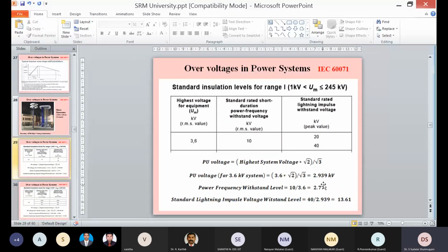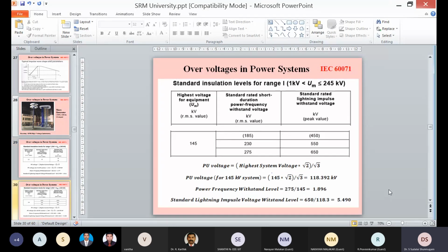Here the key point to be noted is how much increase is happening. For a 3.6 kV system, power frequency withstand level is 2.77 times higher. Lightning impulse is 13.61 times higher. This value please note down. This will be gradually reducing when you are moving to higher and higher voltage. I repeat, the level you are considering will gradually reduce as you move to higher and higher voltage. For example, the next calculation I have shown is for a 145 kV system voltage: your power frequency is 275 kV, your lightning impulse is 650 kV.